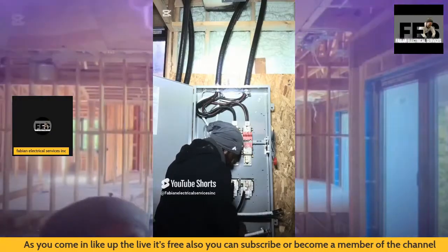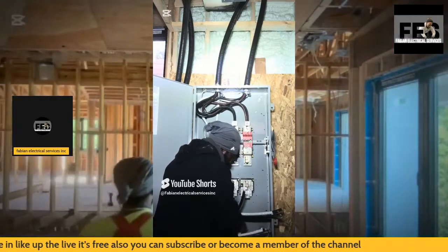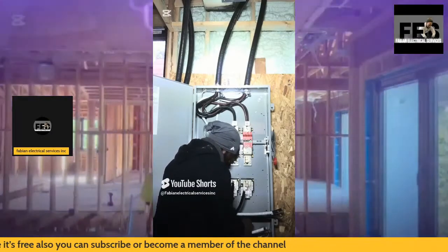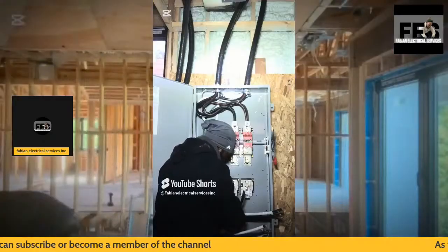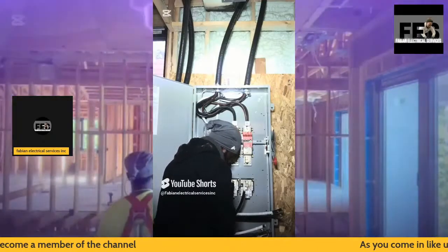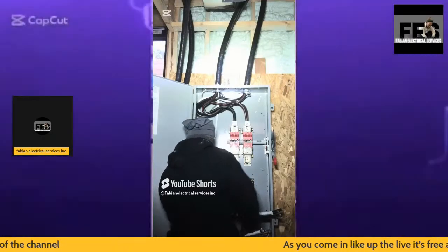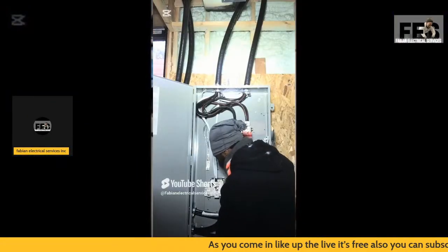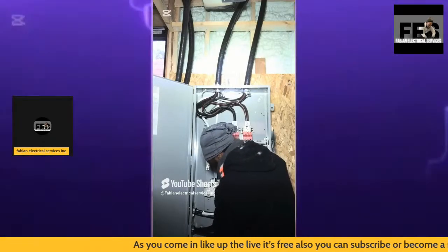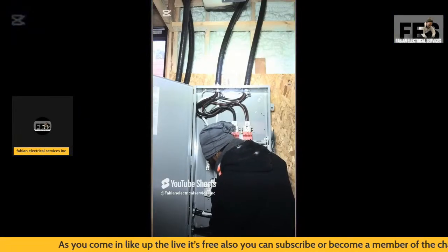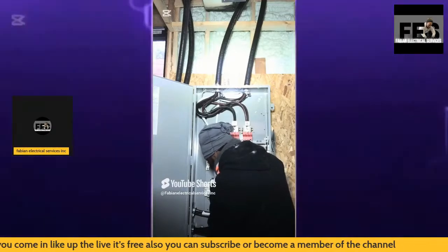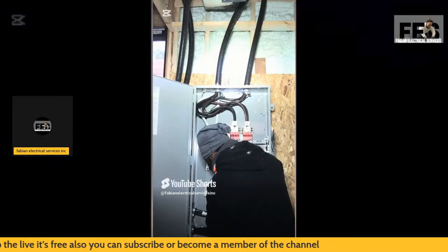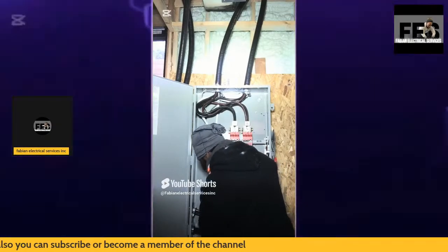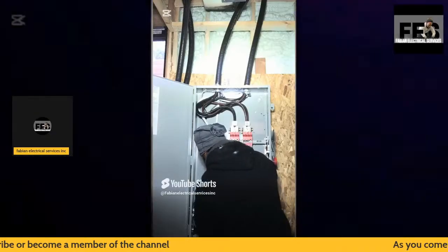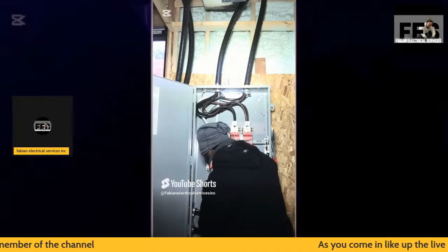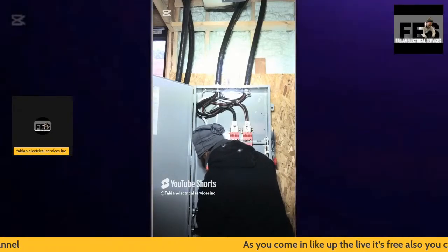Also, you will see me have the cables wired up into the lugs, the main disconnect, the 400 amp disconnect service that I have here that I'm working with, and the cable that I used was 250 kcmil parallel runs. And you'll see all my ground bushings, and everything is grounding the ground wire off, going back to the main ground on the panel.